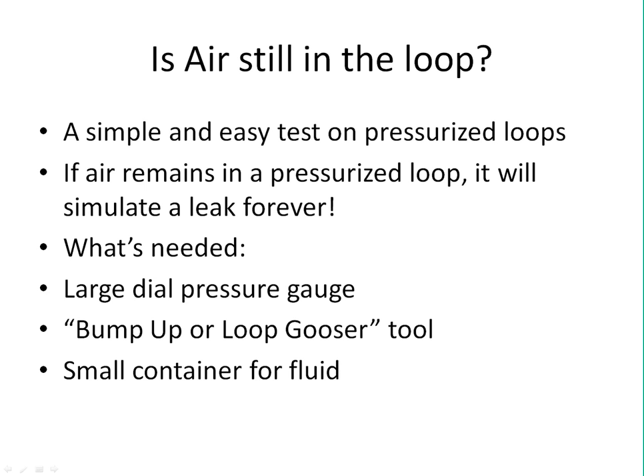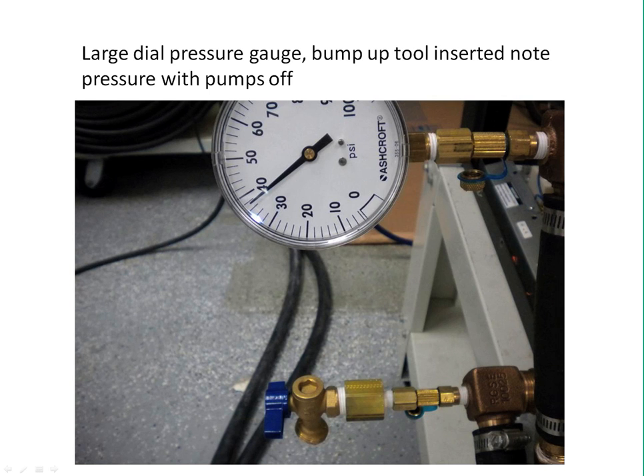Well, you need that, again, large dial pressure gauge. Bring only one to the heat pump with that PT needle attached. You're going to need your bump up, or alternately called a loop gooser tool. And then you're going to need a small container to draw some fluid sample into. Here's an example that you can do. So with the unit powered off, so the pumps are not operating, and it doesn't matter, whatever works best for that configuration, whether the bump up tool is in the upper PT port and the pressure gauge is in the bottom one. If the unit's sitting on a floor or an air pad, you probably will need to do that. You'll see why in a moment.